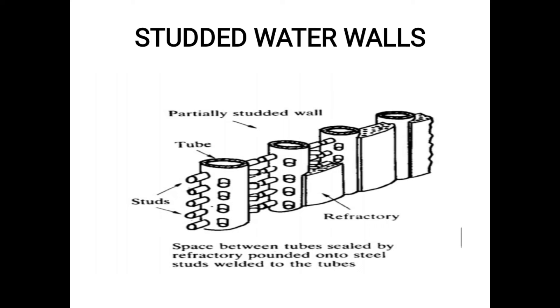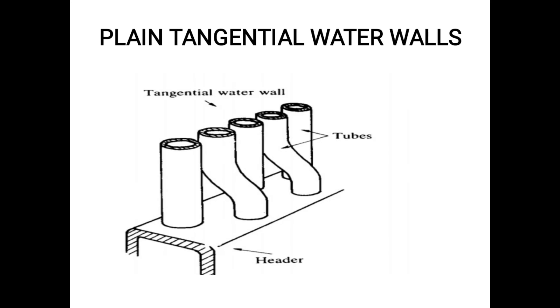The purpose of these studs is to prevent the refractory side and the furnace wall from overheating. In some designs there is refractory behind the studs, and in other designs the refractory is placed on top of the studs — meaning studs are made first and then filled with refractory. Both designs exist for studded water walls.